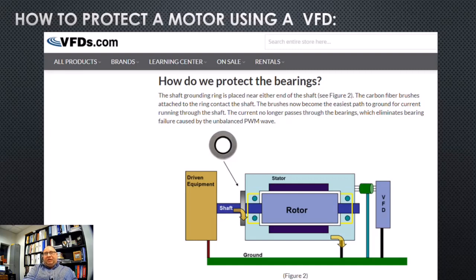So this grounding ring is placed near the end of the shaft, as depicted here in Figure 2, and carbon fiber brushes attached to the ring contact the shaft. The brushes now become the easiest path to ground, all right? Remember, electricity follows the path of least resistance. So instead of going through the bearings, it's going to go through the shaft ring, and the shaft ring is then grounded to earth ground. Okay, so no current passes through the bearings, which eliminates bearing failure caused by the unbalance of the pulse modulation wave. You're going to need to know that possibly for your STAR exam.